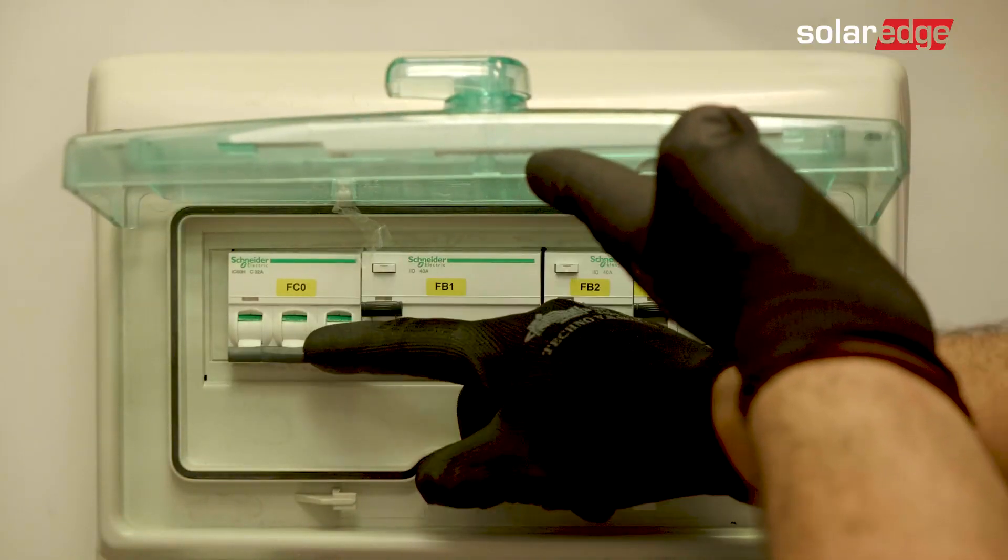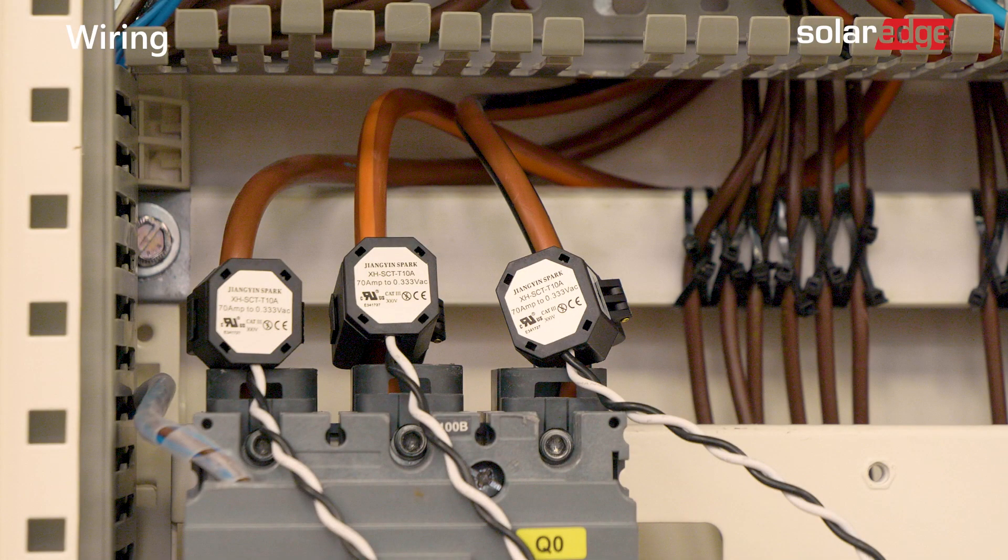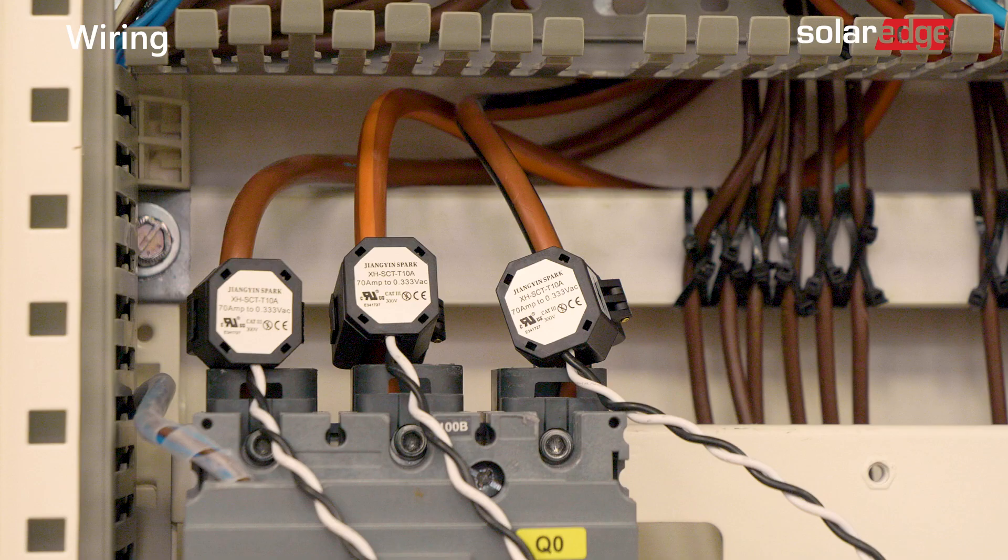Turn off AC power before clamping on current transformers. Now, clamp the current transformers with the arrows pointing to the grid for consumption or export and import measurement.